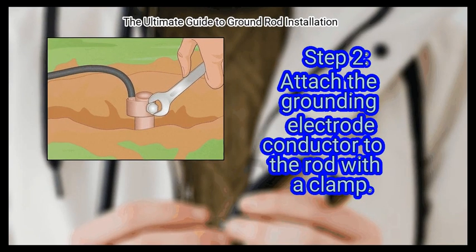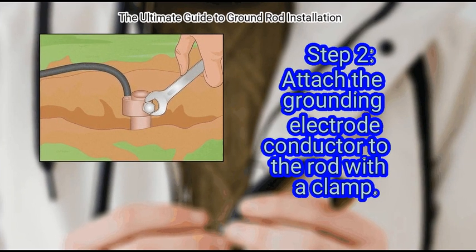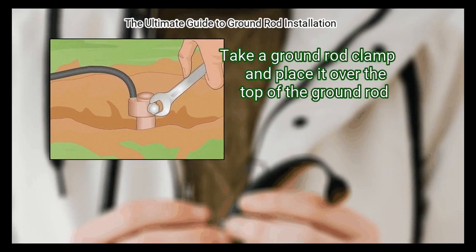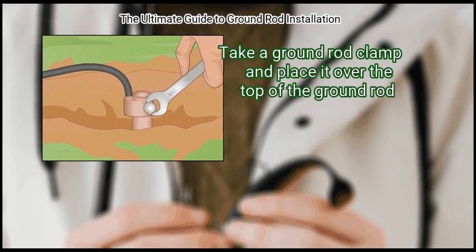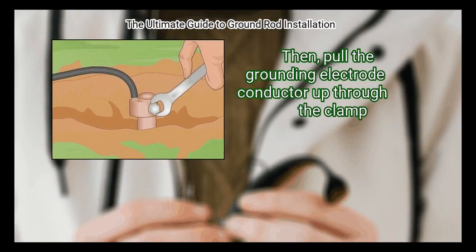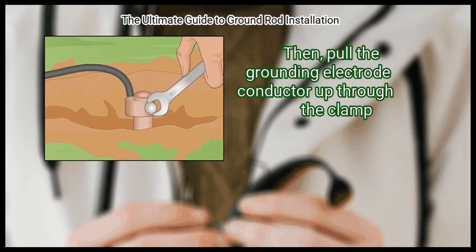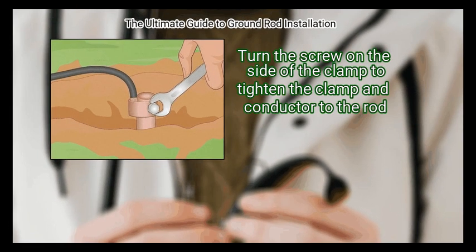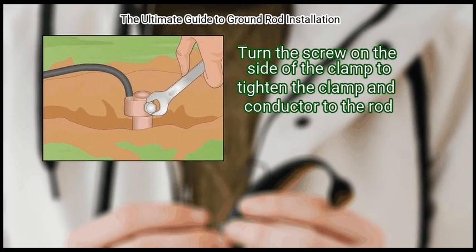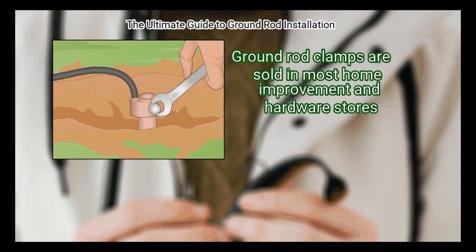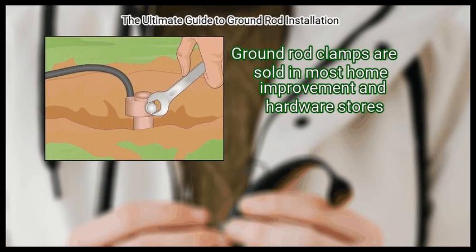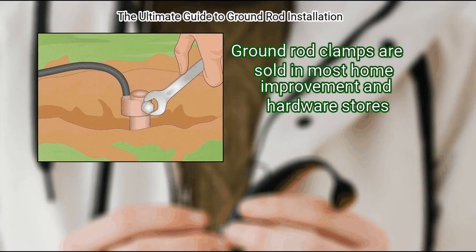Step 2. Attach the grounding electrode conductor to the rod with a clamp. Take a ground rod clamp and place it over the top of the ground rod. Then, pull the grounding electrode conductor up through the clamp. Turn the screw on the side of the clamp to tighten the clamp and conductor to the rod. Ground rod clamps are sold in most home improvement and hardware stores.